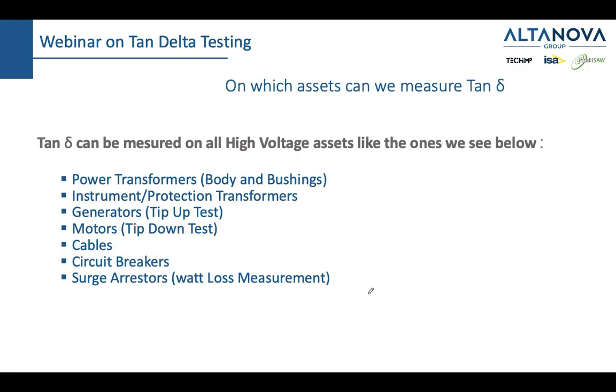On which assets can we measure tan delta? We can measure tan delta on a power transformer, on the body and the bushing of a power transformer, on instrument and protection transformers, so CTs and VTs, on a generator doing a tip-up test, and on a motor doing a tip-down test. The tip-up test is what we call a voltage sweep. Next time we will look into that, but a voltage sweep is when you do a tan delta or power factor test at different voltage levels, let's say 20, 40, 60, 80, and 100% of nominal value. Then you go 80, 60, 40, 20, and you compare those results to see if they are the same.